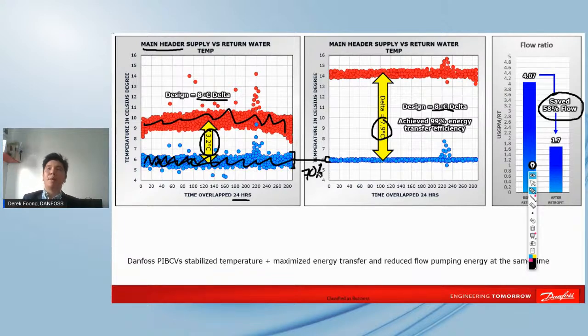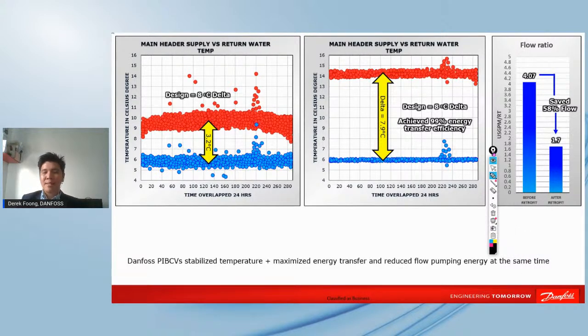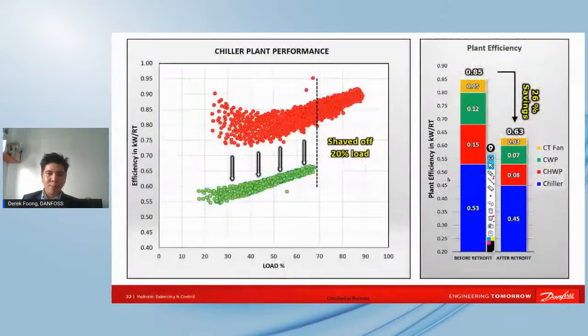And this is the baseline, or I would say one of the key behaviors that we look at in the system. Of course, return temperature can have slightly bigger maximum deviations, but compared to these ones, it's a lot smaller. So there's less surging, because when chillers receive low return temperatures, you start to see chillers making noise, right? Especially centrifugal chillers, single stage.